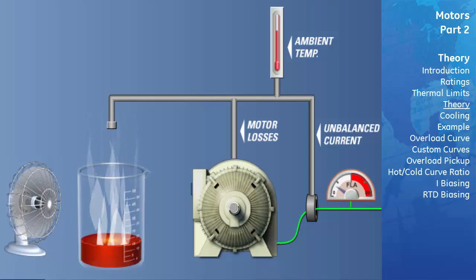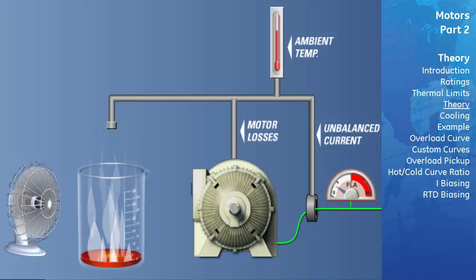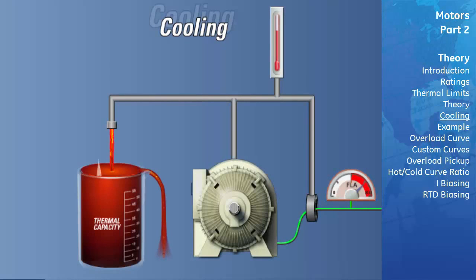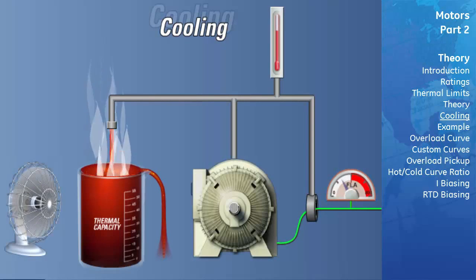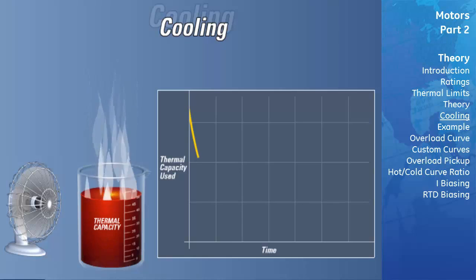The rate at which thermal energy evaporates and the final level it will drop to is a function of the motor data and load current. The vessel is also emptied when the motor is stopped, at a rate based on the stopped cooling time. The thermal capacity used value is reduced in an exponential manner when the motor current is below the overload pickup set point, simulating motor cooling.